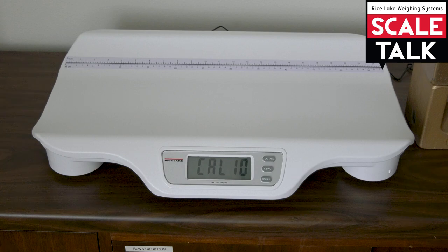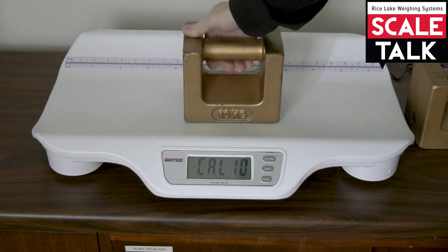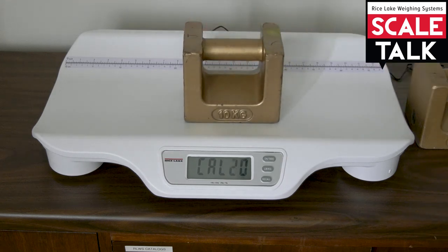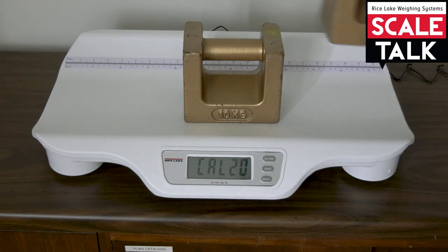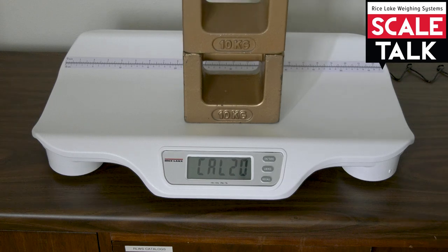Once it stabilizes, it'll request that first 10 kilogram weight. So we'll go ahead and put that on the scale. Give it a moment, and then it requests now a total of 20 kilograms, so we can apply the other 10 kilograms to the scale. It gives it a moment, it says end, and then it comes back out into operating mode and shows us 20 kilograms. So calibration is now complete.